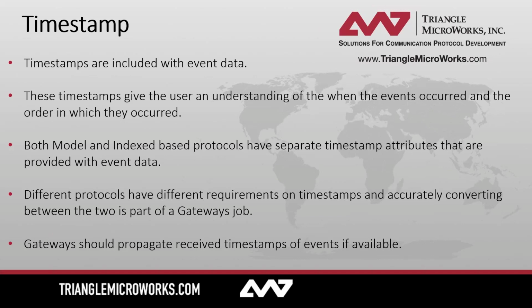Timestamps are a little different. Timestamps are only included with event data, and these timestamps give a user an understanding of when the events occurred, and maybe more importantly, the order in which they occurred. Both model and index-based protocols have separate timestamp attributes that are provided with event data. Different protocols have different requirements on timestamps, and accurately converting between the two is part of the gateway's job.